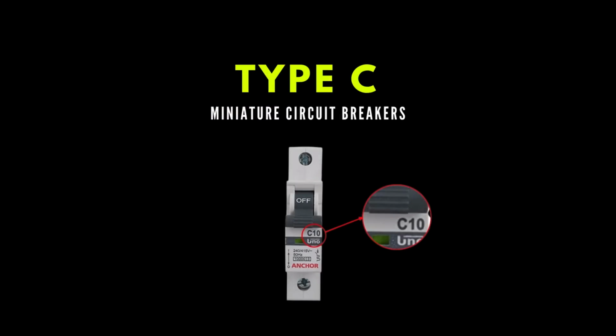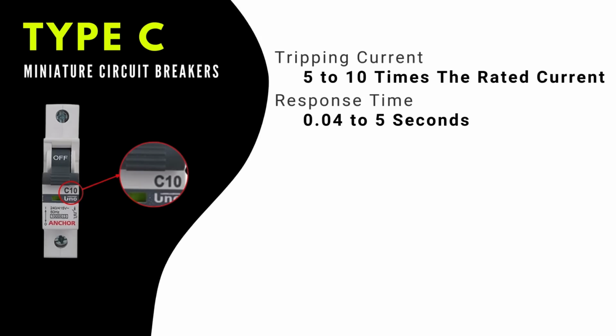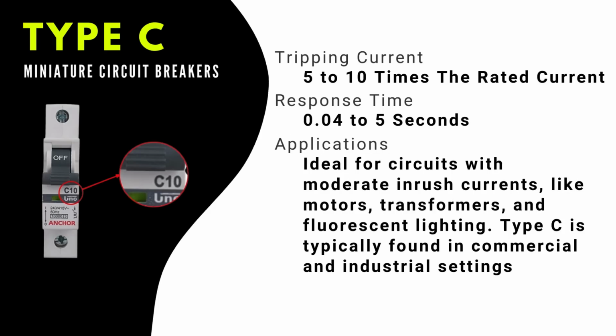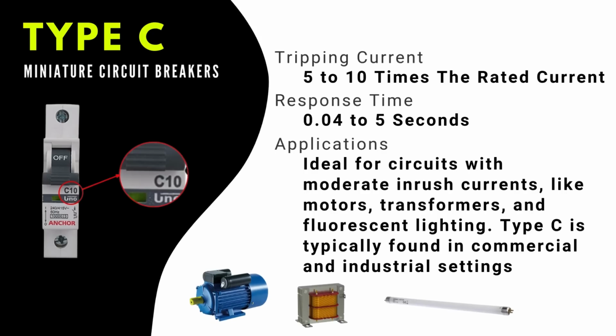Now, Type C MCBs. These trip at 5 to 10 times the rated current, with a tripping time of 0.04 to 5 seconds. They are ideal for circuits with moderate inrush currents, like motors, transformers, and fluorescent lighting. Type C is typically found in commercial and industrial settings.